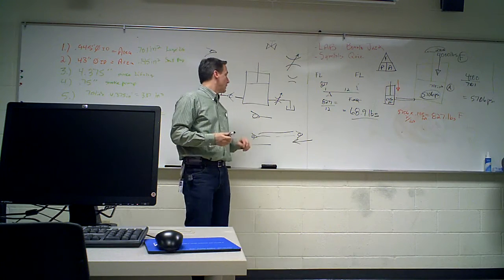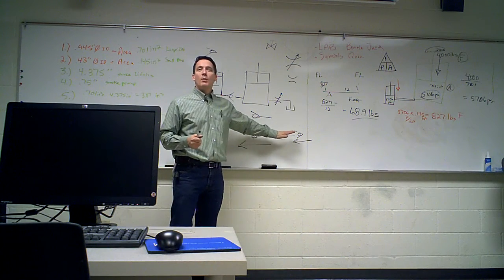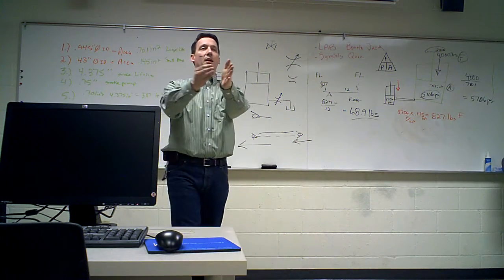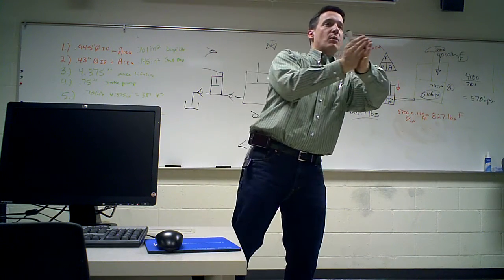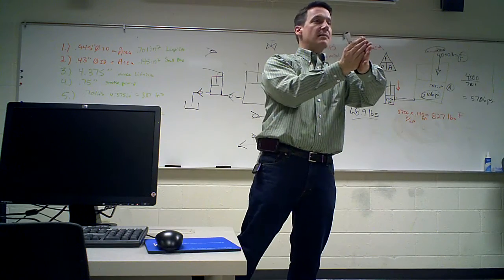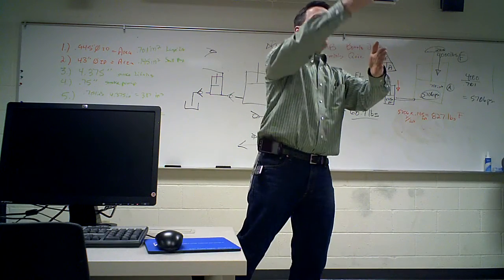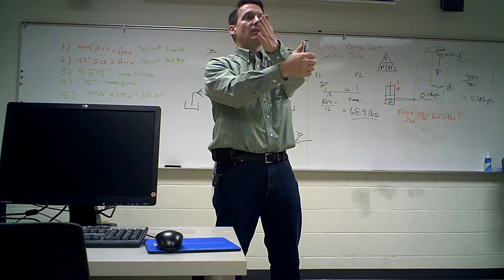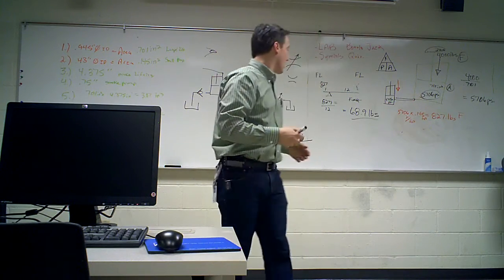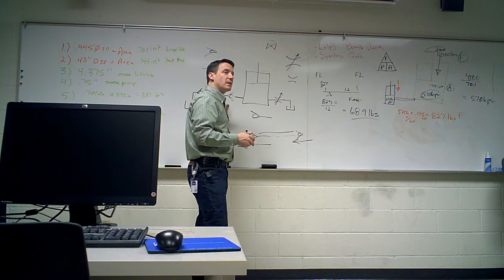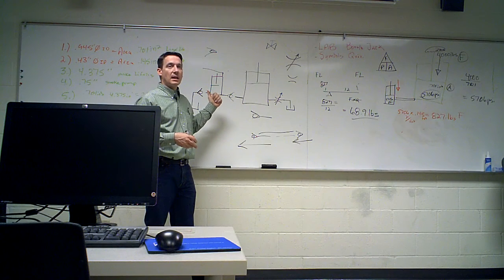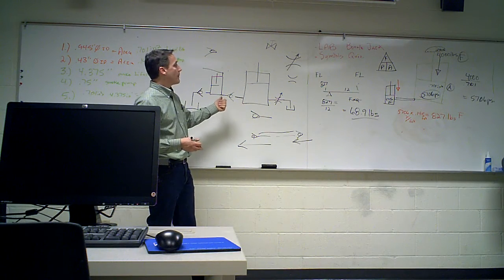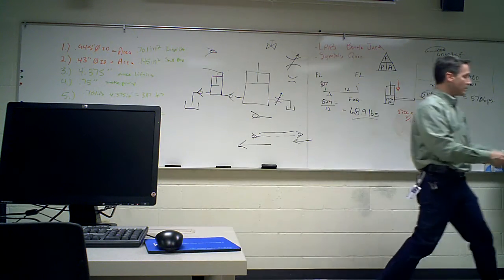All right. But if you open up a diaphragm pump, it's the same principle. It's going to have a diaphragm sitting in there. You're going to pressurize one side. It pushes peanut butter, gas, whatever on one side, pushes it up through a check valve. Comes back the other direction, allows it to come through a different check valve. Back and forth. So this principle of a pump is something that's pretty good to understand when you start ripping into any type of even complex pump. All right, so where are we at next?